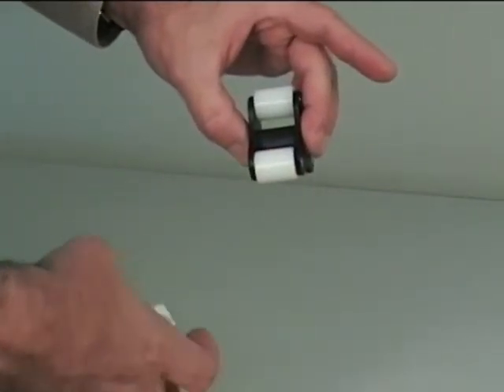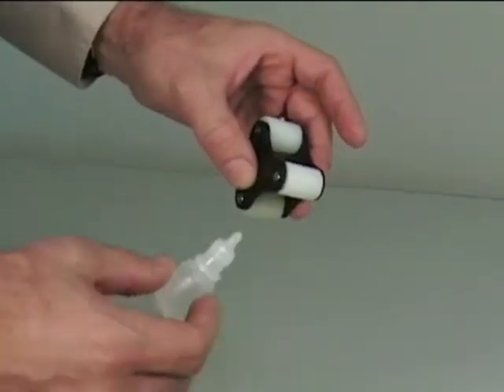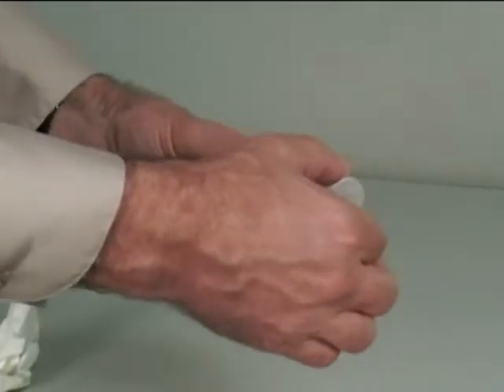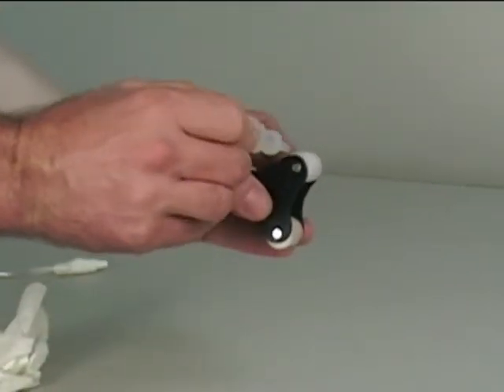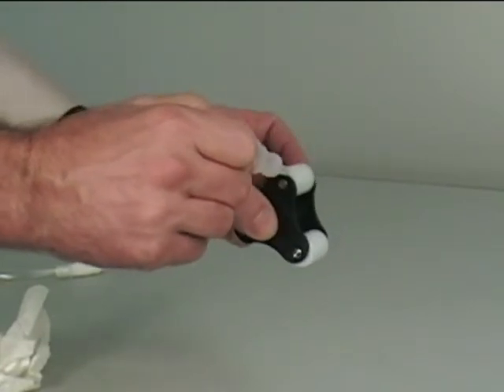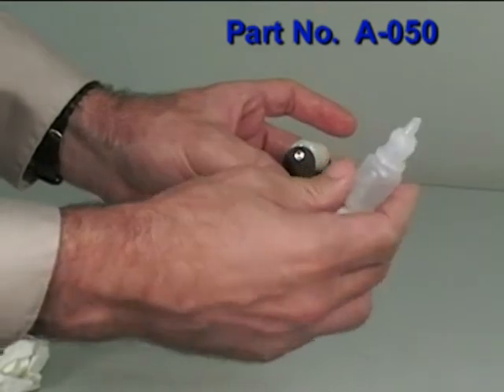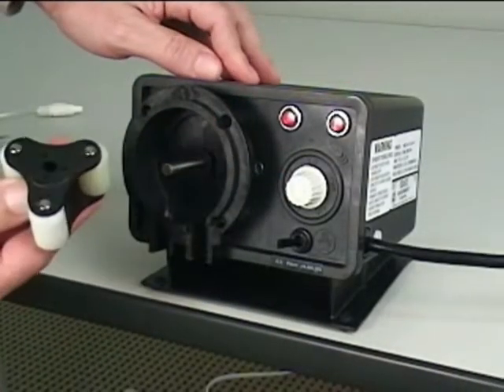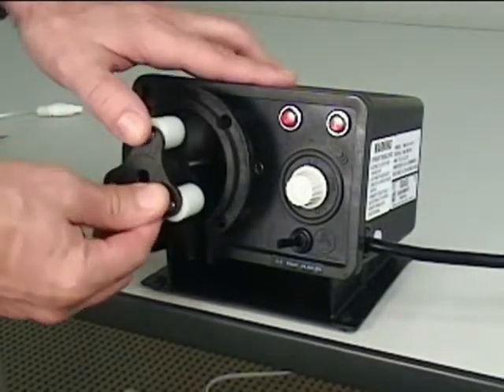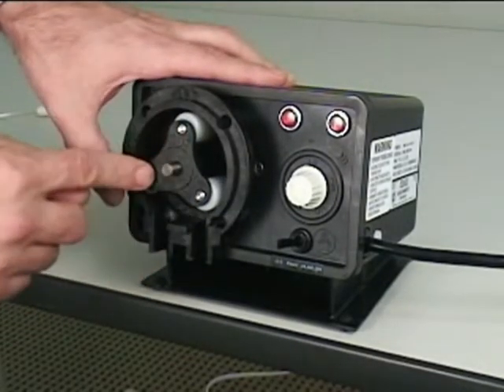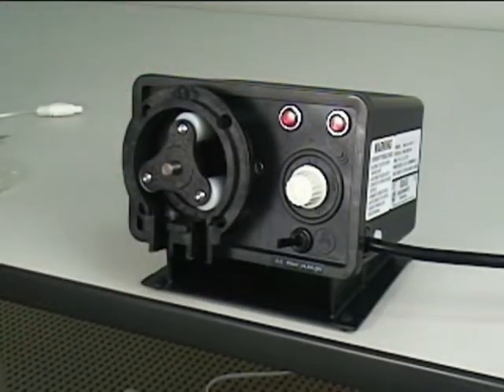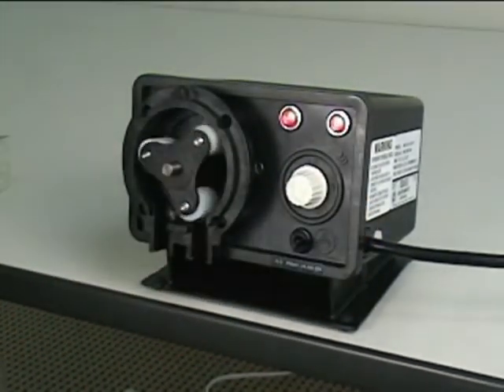Be sure the surface of each roller is smooth and that all of the rollers spin freely. Check that there is only a slight amount of play between the rollers and the axle. Rollers that have too much play will prevent the tube from being properly squeezed and will reduce the pump's output and pressure capability. Replace the roller assembly if necessary. Apply a small amount of light silicone oil only to each roller.